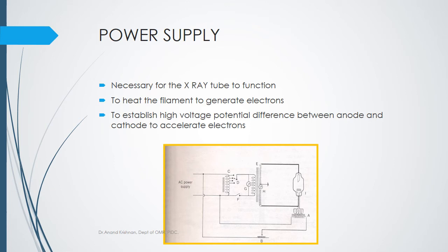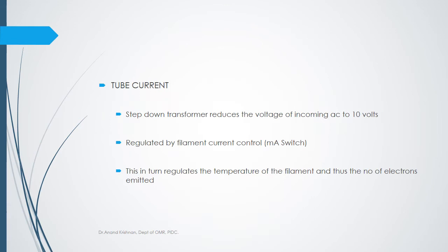Regarding power supply, the x-ray tube requires: first, current through the cathode to produce thermionic emission — heating the filament to generate electrons; and second, high voltage between anode and cathode to accelerate these electrons from cathode to anode with enough intensity to strike the anode and produce x-rays. The two key values are milliampere (mA) and kilovoltage peak (kVp).